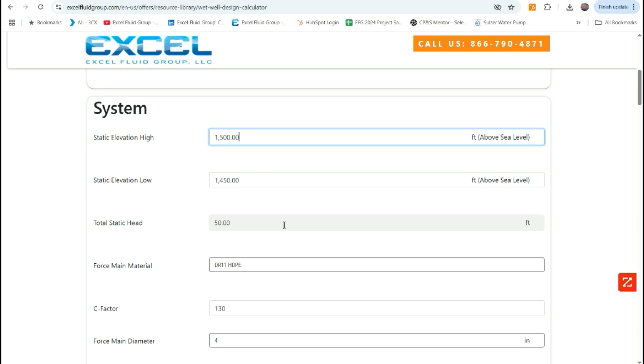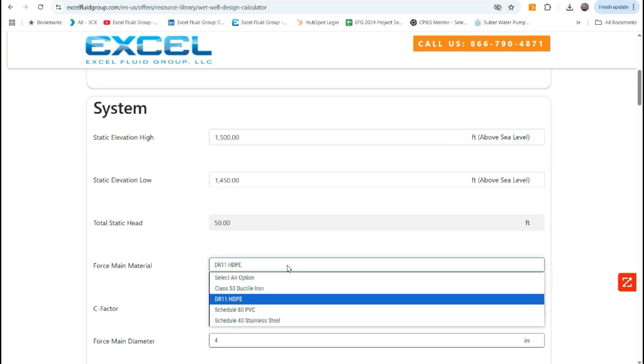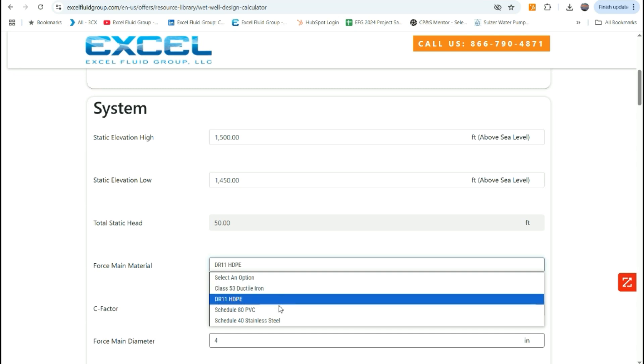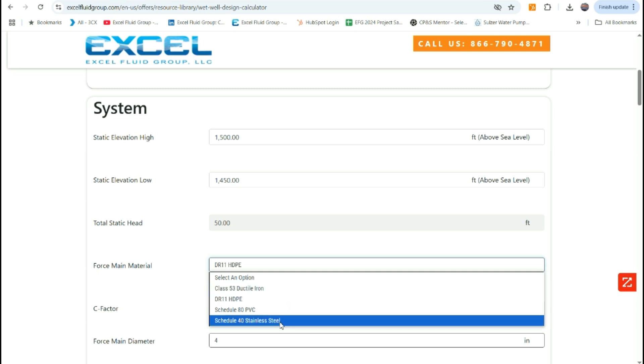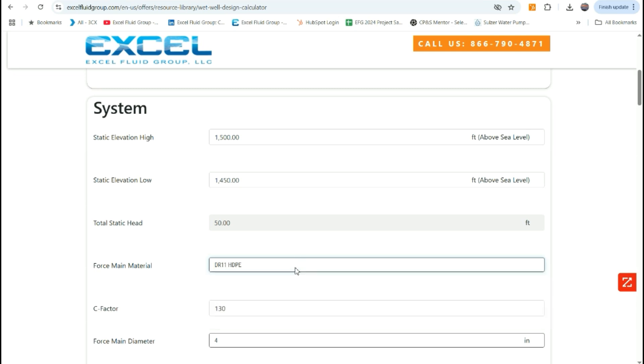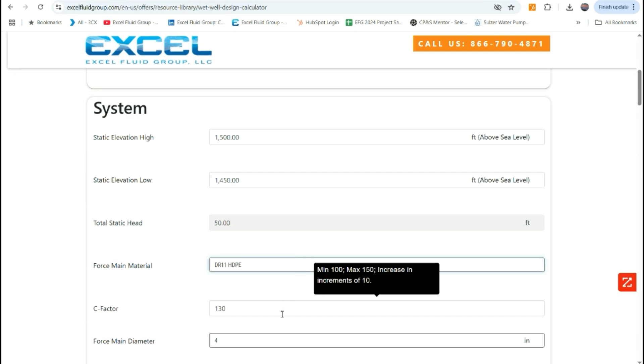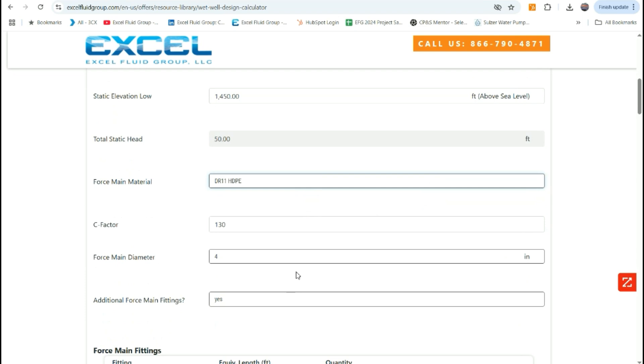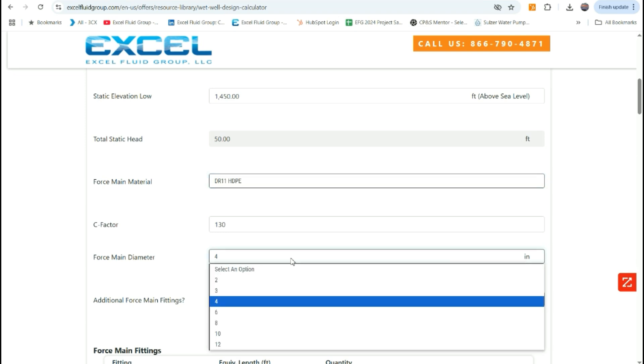From there, we can move on to selecting what our force main material type is. We've got a few options here. For this case, we'll select HDPE, and then that automatically puts in a C factor value, which you can adjust if you want to default to 100. In this case, we'll leave it at 130. From there, you'll select your force main diameter.